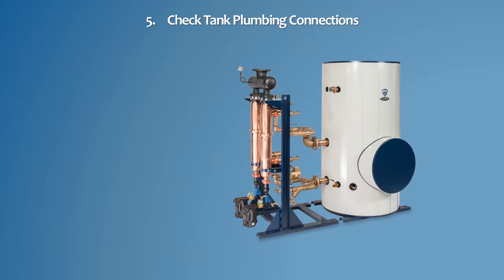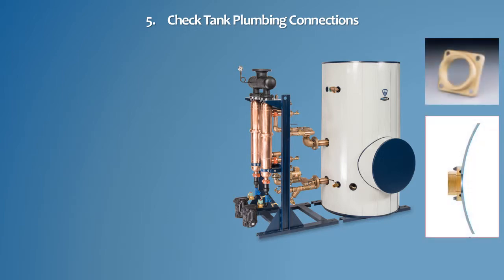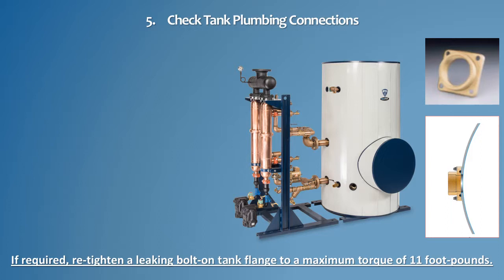With the tank filled, check all tank flanges and pipe thread connections to ensure they are watertight and tighten as necessary to avoid leaks that will damage the tank insulation. The Cobrex storage tank incorporates bolt-on bronze tank flanges sealed by an O-ring gasket at each plumbing connection. A cover plate attaches to the jacket opening at each plumbing connection, which can be removed to access a bolt-on flange. If required, retighten a leaking bolt-on flange to a maximum torque of 11 foot-pounds.